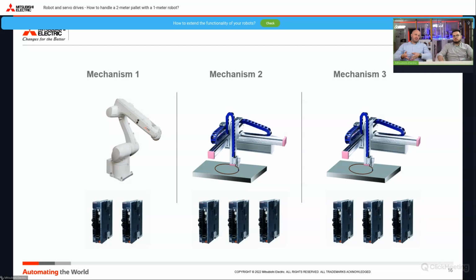This possibility means a reduction of costs. For example, if you have a whole line and at the end of the line you don't need the robot, only the manipulator, you can use the robot controller to build such a manipulator. That is, as I understand it, we have a lot of space for cost optimization of the master controller. But I also see an extremely important thing: a robot controlling axes operating in the collision space will be easier to control, because we don't have any delay in data transmission about position, etc., between the robot and the master PLC. And as the PLC controls the drives, we simplify writing the control because everything is inside the robot.